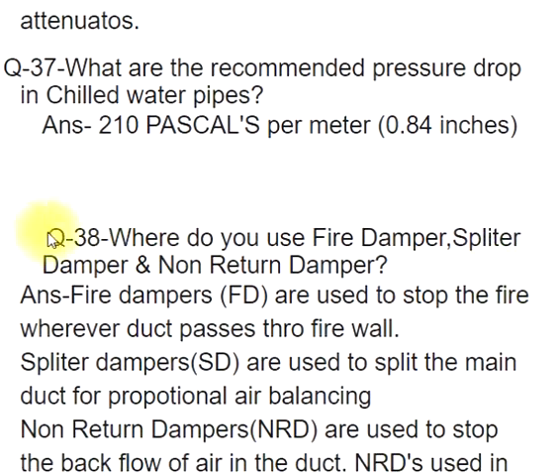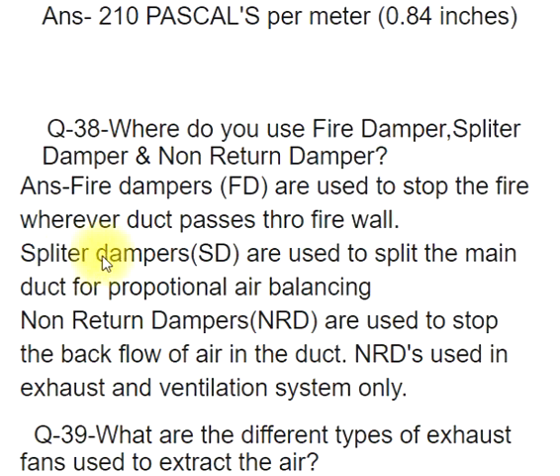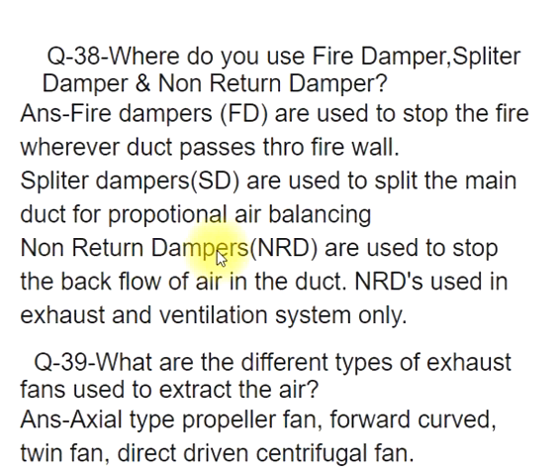Q38: Where do you use fire damper, splitter damper, and non-return damper? ANS: Fire dampers (FD) are used to stop fire wherever a duct passes through a fire wall. Splitter dampers (SD) are used to split the main duct for proportional air balancing. Non-return dampers (NRD) are used to stop the backflow of air in the duct; NRDs are used in exhaust and ventilation systems only.